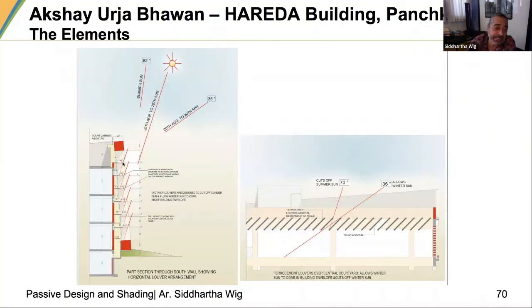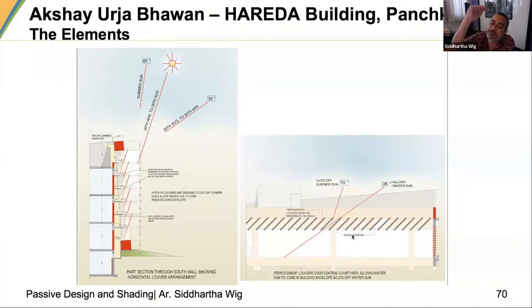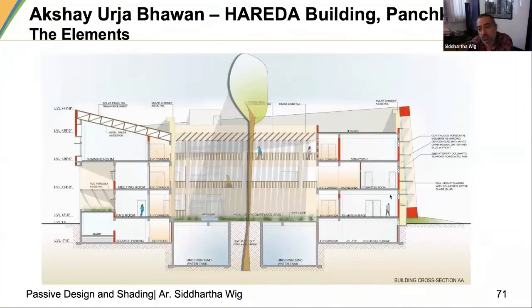The louvers on the roof were originally to be ferrocement but eventually we used a metal frame with aluminium-clad sheet on top. These were calculated to allow only winter sun to come in — during summer only diffused light enters the central courtyard. In section the solar chimneys are visible on the south face along with glazing at an angle. The horizontal shades also provide a maintenance corridor so you can walk along and clean the windows without needing a separate device.